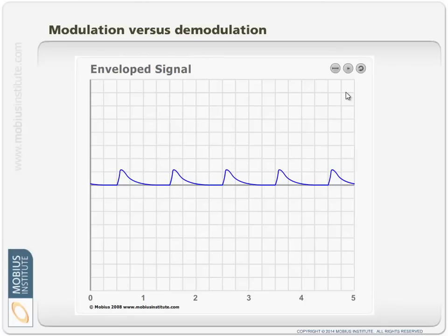So again, I can use that enveloping technique to get rid of the low frequency, high amplitude vibration and just focus on what results when you get metal to metal contact. Same with broken rotor bars. You can see a situation with a broken rotor bar, because of the crack, that it creates this same stress wave, and you may pick that up, and there's other situations as well. But it doesn't rely on a modulated signal in the first place. It's just that we're generating stress waves or shock pulses, or we're exciting resonances in the accelerometer or the machine itself.